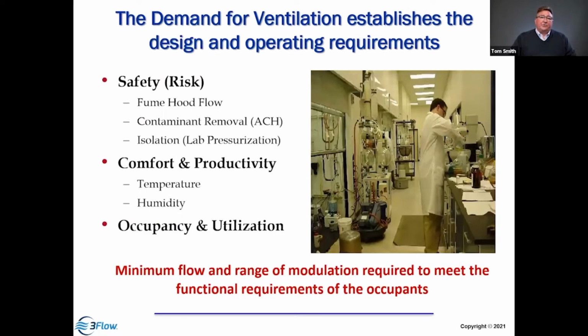So we have to boil that down to what we call the demand for ventilation. How do we take these requirements and establish some operational specifications and some design requirements that enable us to design and effectively operate the systems to meet the needs? So first and foremost, we look at safety. What are the occupants doing? What type of hazards are they working with? How much flow is required for the fume hoods? What kind of airflow is required for dilution in terms of air changes per hour? And what is required for isolation and pressurization from the space?